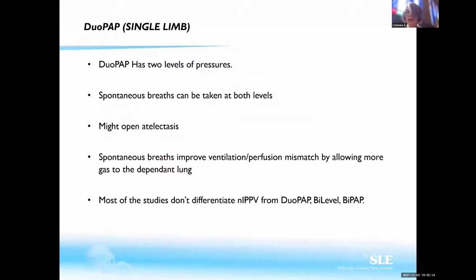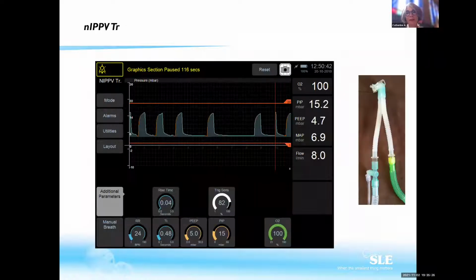And here, the settings that you might set, usually what we see is the PIP, which might be only 2 to 3 millibar above the PEEP that you set. It's quite a common setting. In some ventilators, what you have now is NIPPV trigger. This means that the ventilator will synchronize with your patient. Some of them might use a grasp-by, for example, a capsule, which will be put on the abdomen. When the patient takes a breath, it will expand the Graseby capsule, where you will have a decrease inside. It will sense it, and then it can pick up the breath.